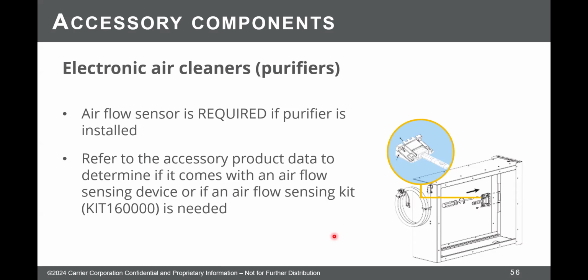Historically, we've just interlocked this to the EAC terminal on the furnace, but apparently that's not good enough anymore. That just says the fan is supposed to be on. It doesn't prove the fan is actually on. So now we have to have a pressure switch or a sail switch or something that actually proves airflow.